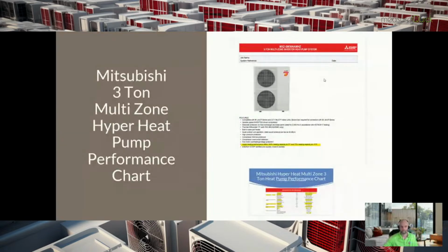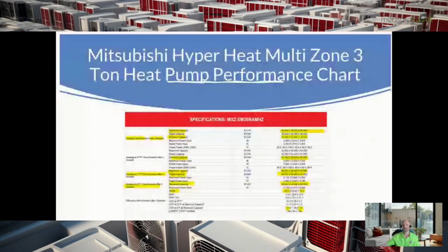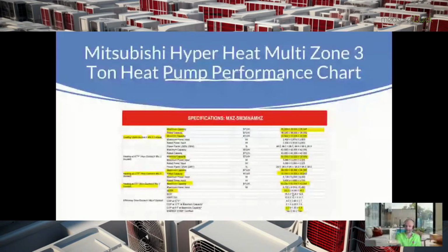And now let's look. This is where it gets real fun, guys. Let's get into the Mitsubishi 3-ton multi-zone Hyper-Heat heat pump. Now, with these multi-zone systems, there are so many different pieces of information that you have to pay attention to when you are sizing. Some of this stays the same, but some of it changes depending on the piece of equipment. Notice you have cooling and heating, non-ducted, ducted, or mixed. There are sometimes different capacities and different parameters depending on what configuration of heat pump you're using. So you really got to go into the data and pay attention to this stuff.